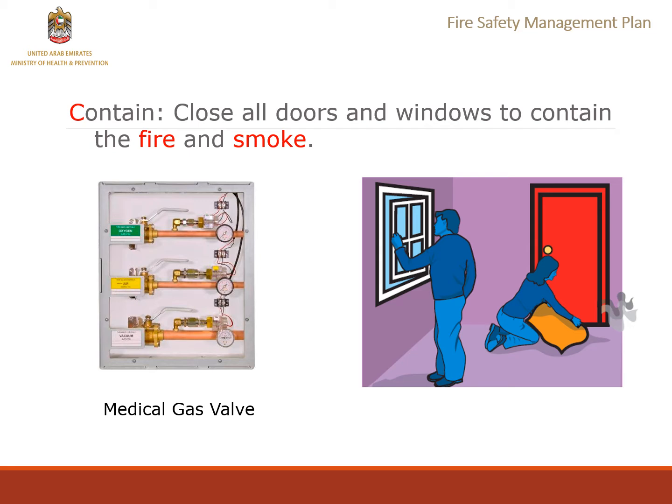Sorry. When do you shut it off? After code green, the code for evacuation, has been activated and patients on ventilators have been provided with enough ambu bags, portable cylinders, and enough staff to assist. Then only it's safe for the fire warden to shut off the medical gas valves.